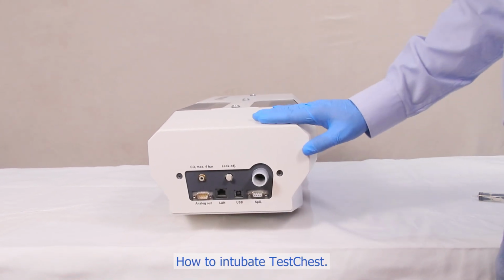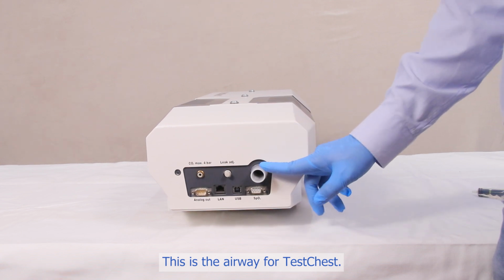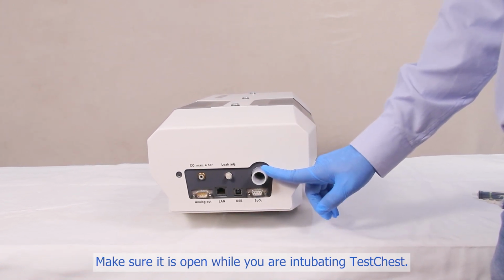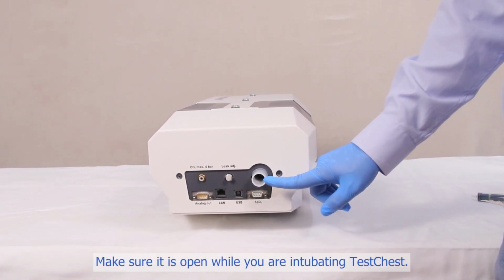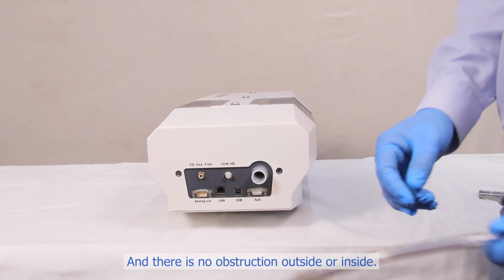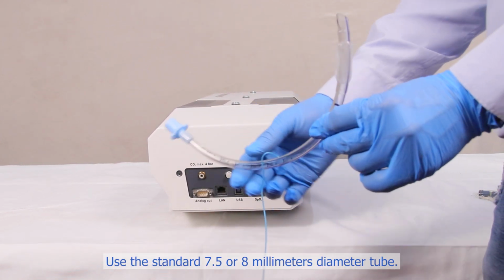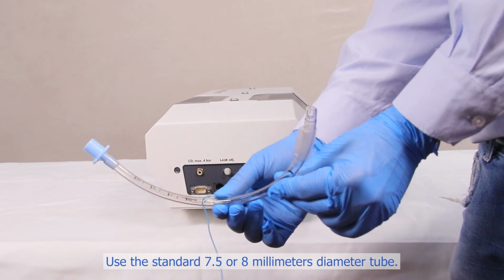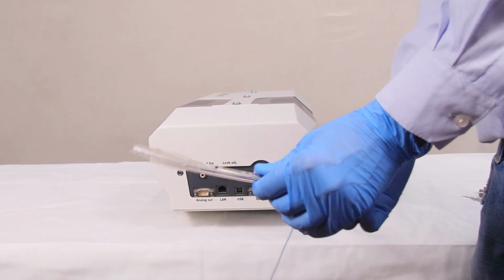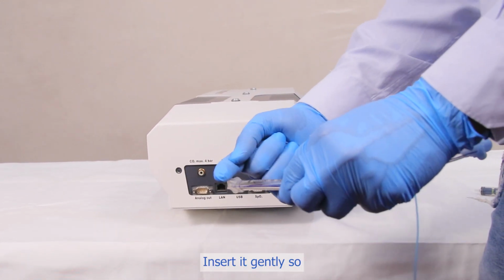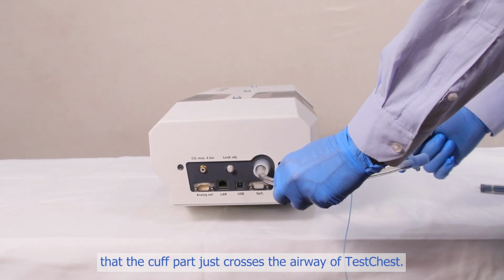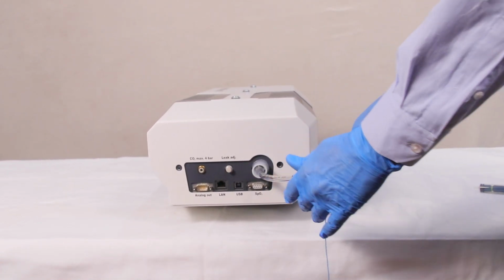How to intubate TestChest. This is the airway for TestChest. Make sure it is open while you are intubating TestChest, and there is no obstruction outside or inside. Use the standard 7.5 or 8 mm diameter ET tube. Insert it gently so that the cuff part just crosses the airway of TestChest.